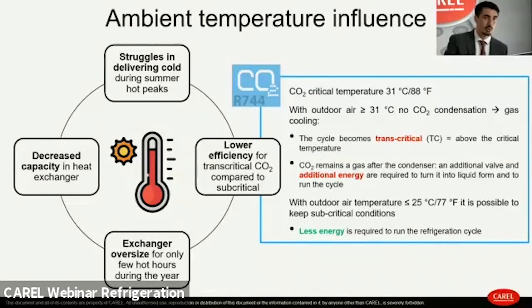Let's talk a little bit about the ambient temperature influence on gas coolers. In the last years, we saw something quite evident to all of us: there has been an increase in temperature, especially during summer peaks. Considering that many plants and systems were designed and installed some years ago, even 10 or 20 years ago, it's obvious that the conditions were different. So in some cases the heat exchangers are dimensioned for other conditions, and sometimes right now, during summer most often, they are not enough anymore to produce the heat rejection that is needed.